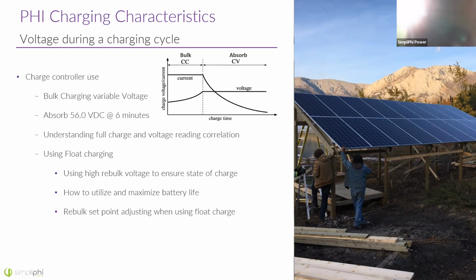After that point, we're going to keep the battery at a constant voltage. For our batteries, that setting is 56 volts. We're just going to do that for 1/10 of an hour, and that's to top off the battery. So the bulk part of the cycle is the majority of the charging cycle. It occurs at constant current. As we get the battery to top off, we have to slow down the current rate. So the current drops off rapidly, but we keep that voltage at an absorb.